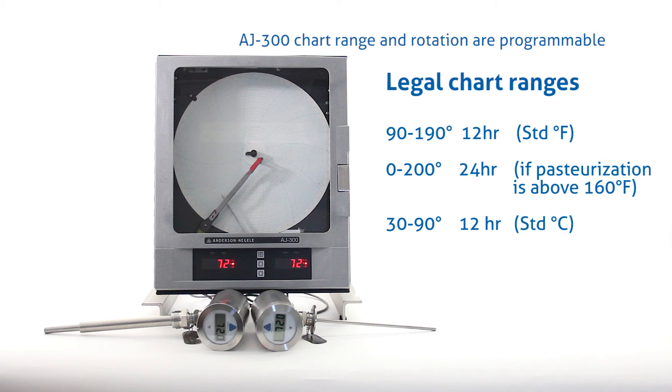There is also a 0 to 200 degree, 24 hour Fahrenheit chart. That can only be utilized if you are pasteurizing above 160 degrees Fahrenheit, and that chart will have two degrees per division. The Celsius chart is a 30 to 90 degree, 12 hour chart. That is the standard Celsius chart.